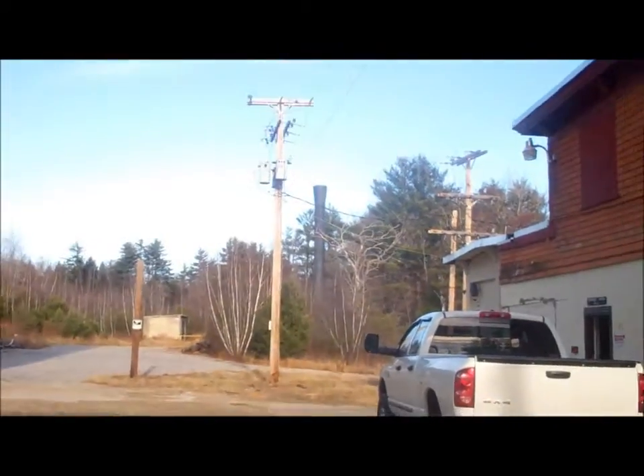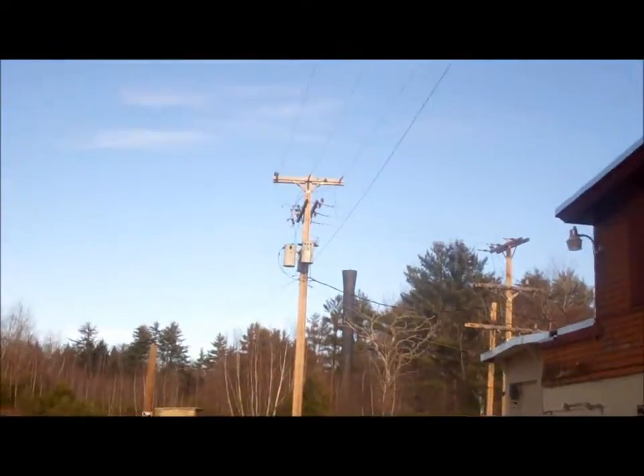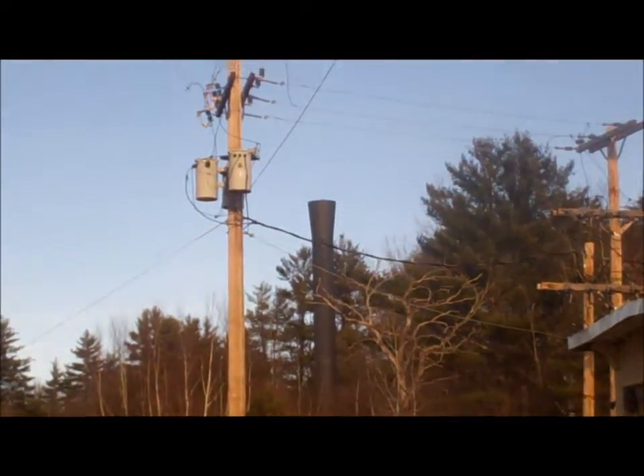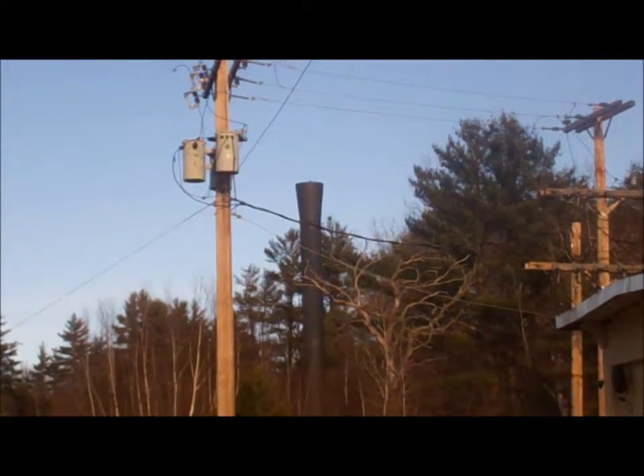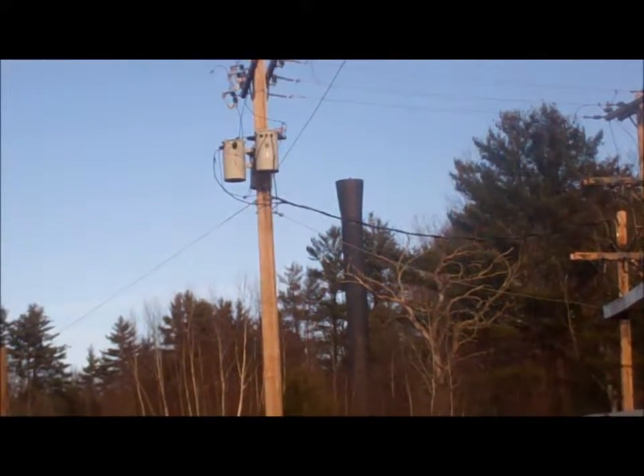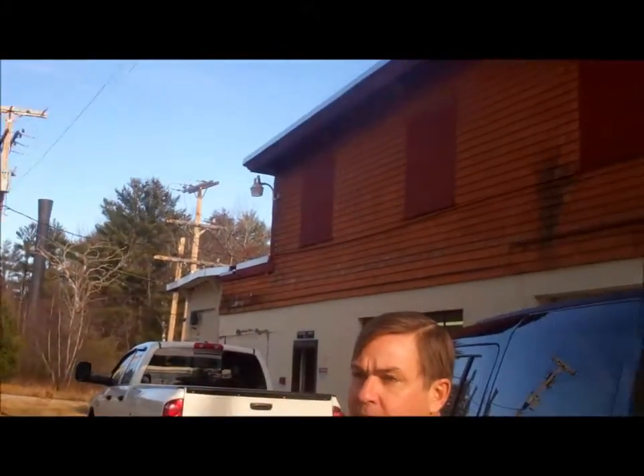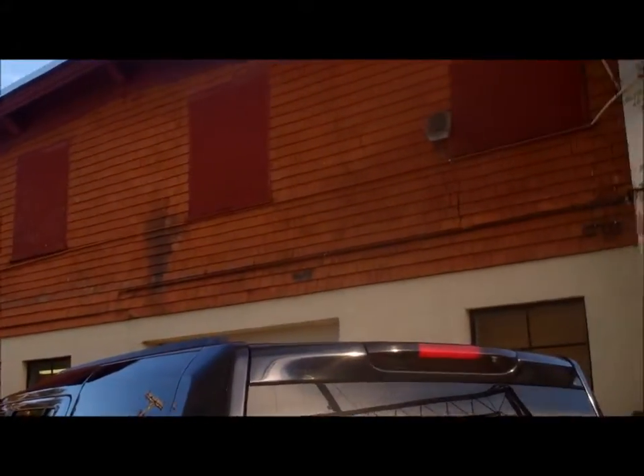All right, so our pipe is 4,200 feet from the corner of the building up to the dam. It's 6'6" inside diameter. It carries about 2,200 gallons of water a second into the plant. We have three Francis machines in this building, and we have a Francis in this building as well, so we have a total of four machines. We have a 1.5 megawatt output.